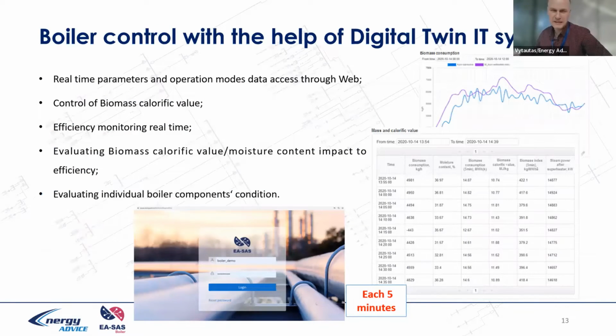Coming back to EA-SAS Boiler as a system, we of course give you access through the web to real-time data. We can control and we can meter biomass calorific value and biomass consumption every 5 minutes. We do this estimate every 5 minutes. You may ask how we can do this estimate every 5 minutes. Because we have inside a couple hundred equations. We use online data and do reverse engineering, reverse mathematics, back until we calculate the water content in the fuel and the biomass consumption.